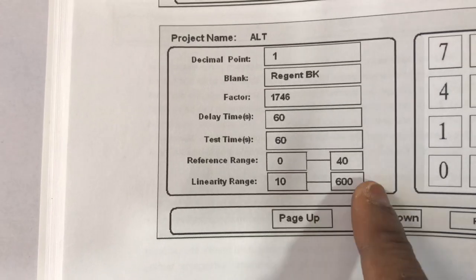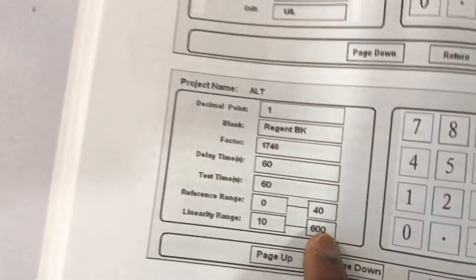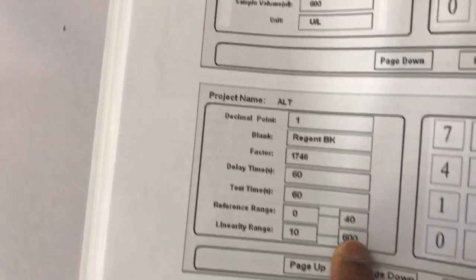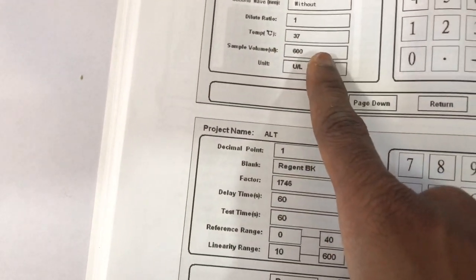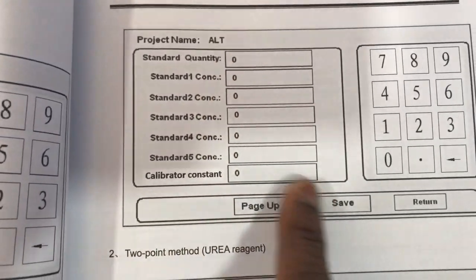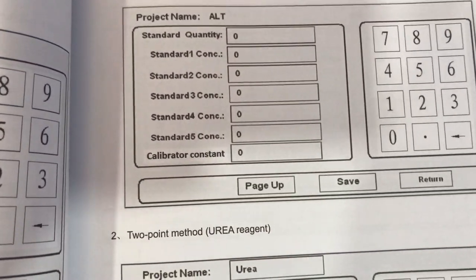Then enter the reference range. For a typical kinetic method, because the manufacturer provides the factor, you don't need to run a standard — the standard quantity will be zero. That's how to program for a kinetic method.